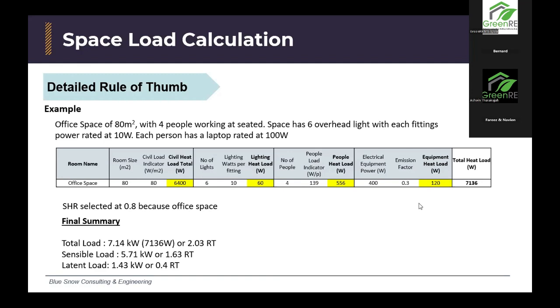And then I select the 0.8 sensible heat ratio because it's an office space. This is if you are using the rule of thumb approach. That's why you select this. The actual detailed part I will show you in the psychrometric section of this webinar, on how to actually calculate that without having to rely on these rules of thumb. So this gives you the final summary of the space. My space is going to take this many kilowatts of cooling, or in RT it is 2.03. What is the load breakdown going to be like? This gives you the overall picture if you're using the detailed rule of thumb approach.